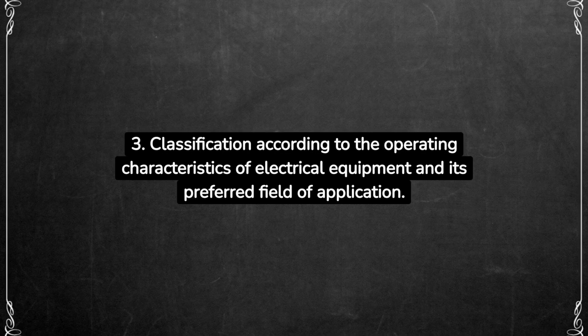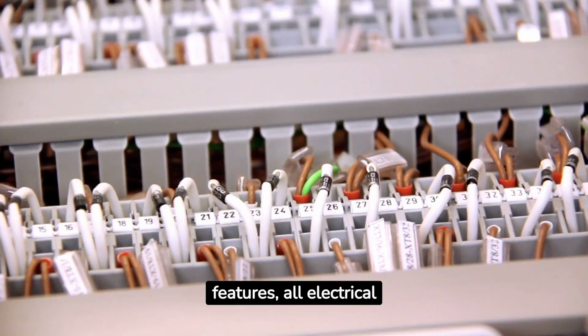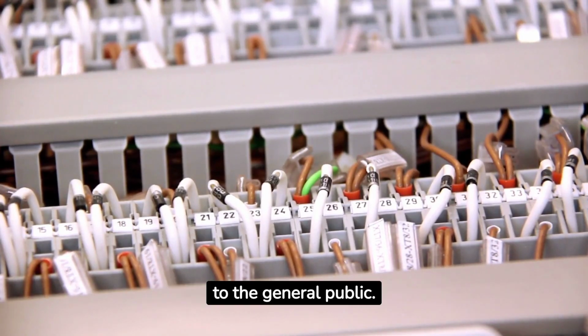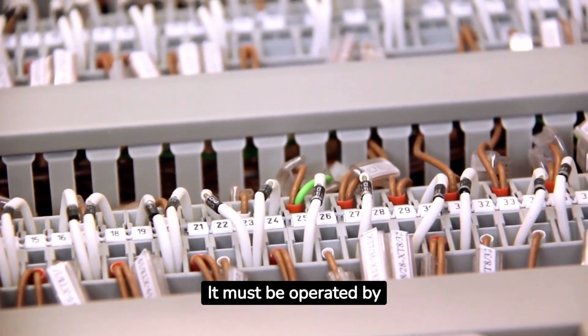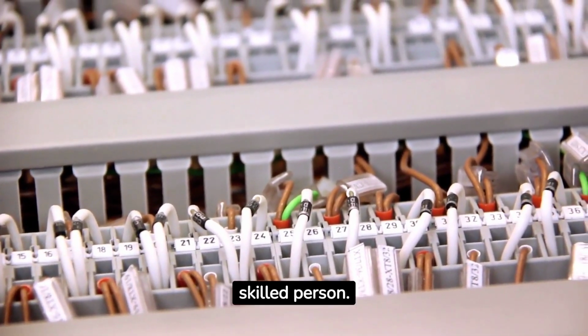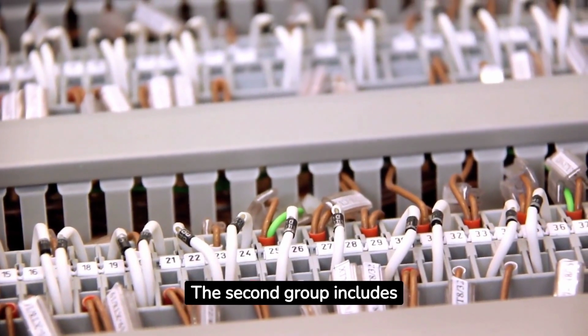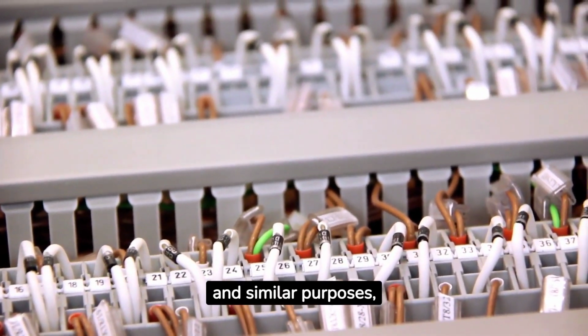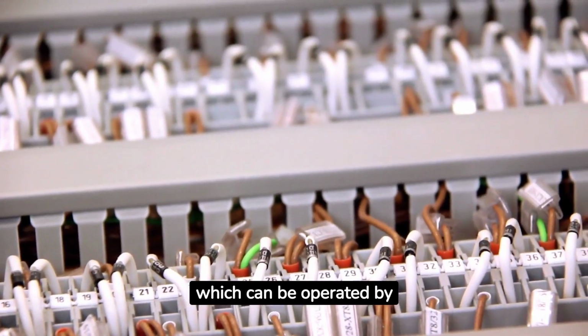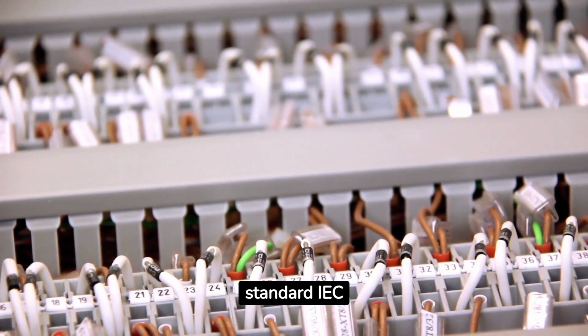3. Classification according to the operating characteristics of electrical equipment and its preferred field of application. According to the operating features, all electrical equipment is divided into two groups. The first group includes electrical equipment that should be inaccessible to the general public. It must be operated by instructed and electrically skilled person. The second group includes electrical equipment of household and similar purposes, which can be operated by ordinary persons.